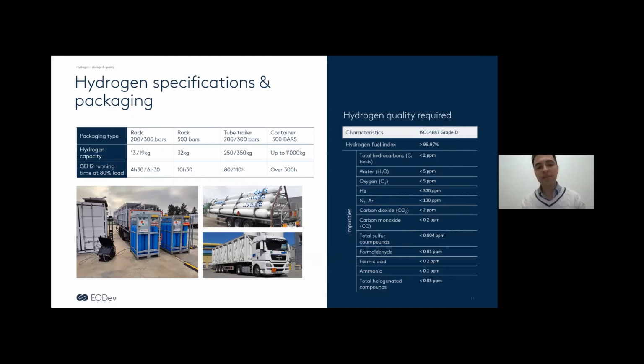We estimate a consumption of around 4.24 kilograms of hydrogen per hour at full output, which is what our power genset needs to provide 100 kVA. These are examples of hydrogen storage and the autonomy we can achieve. For small customers and applications, we can use small bundles starting at 13 kilograms, up to 1 ton for huge consumption with multiple units. That's basically the case for Nigeria, since they'll be consuming 2 tons per day roughly, so we need bigger solutions for hydrogen storage.